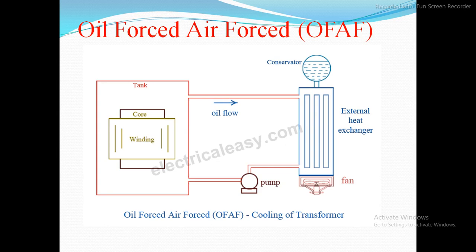So you can see in this method, oil force, air force. Here both are forced. The oil is also forced; the circulation of the oil is done by using the pump, and the heat is removed from the heat exchanger by using the fan. So in this method the circulation of the oil is not due to natural convection. Here we have used a pump. Why is the pump used? The more circulation there is, the more heat is removed, and the more cooling effect we get.